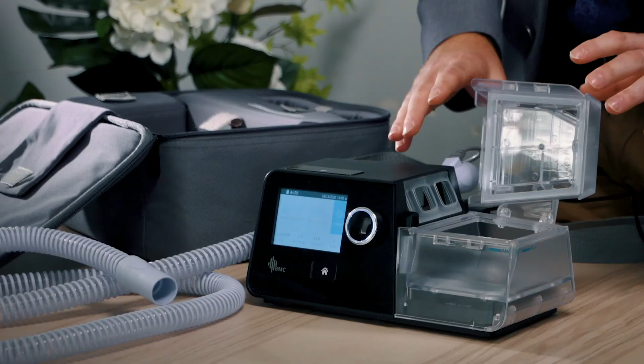For care and maintenance of the device, make sure there's no debris building up on the heater plate itself. Take it to the tap often to make sure that it's cleaned and flushed. If you're ever moving your BMC device, make sure there's no water in the humidifier chamber, because you don't want any water spilling back into the device and creating a mess or potentially damaging the circuitry of the device. So always move it with an empty humidifier chamber. All BMC G3 series devices have a 5-year warranty as standard. If you ever experience any issues with your BMC device, please contact your BMC provider.